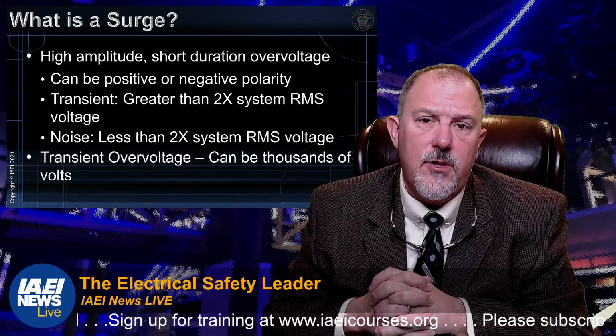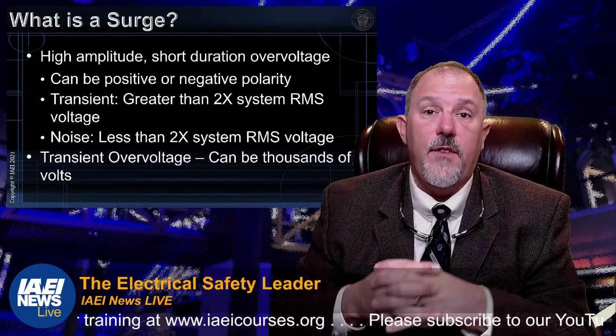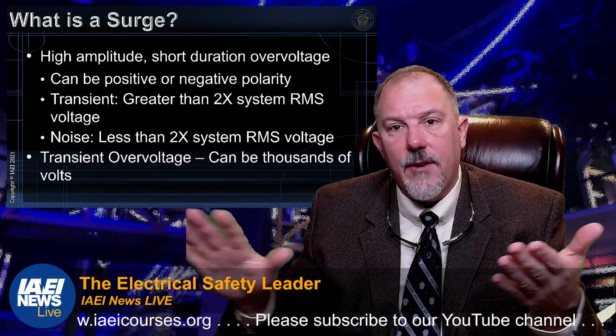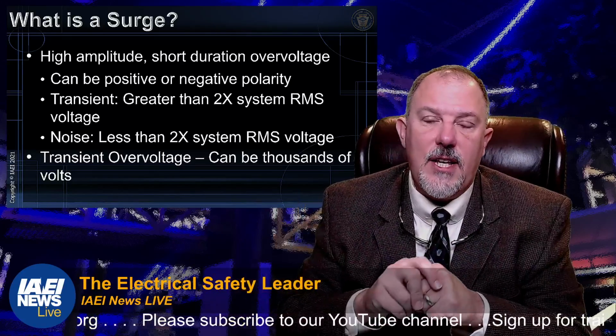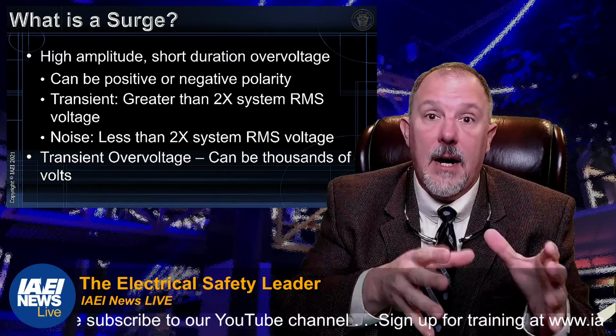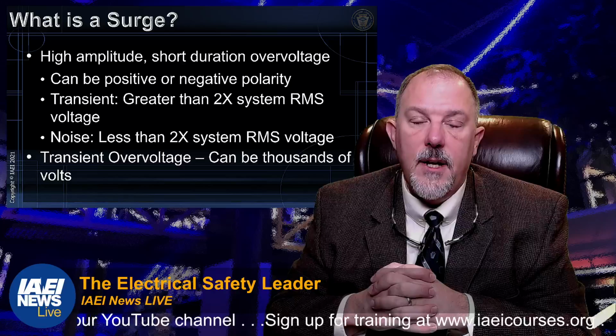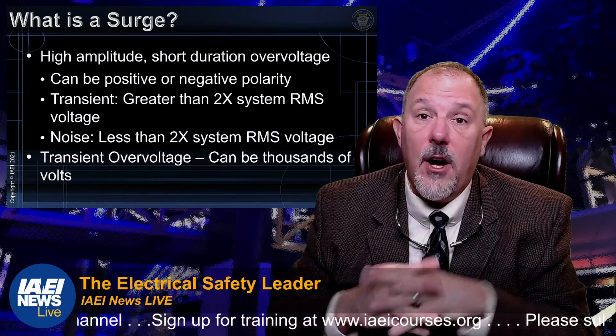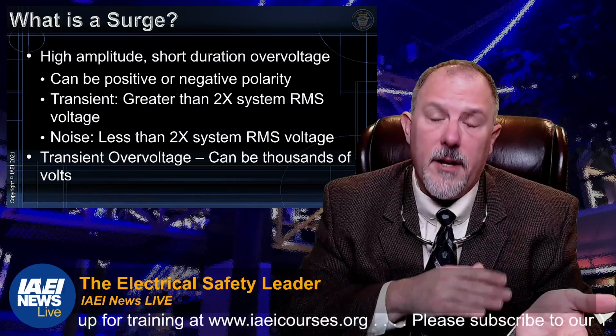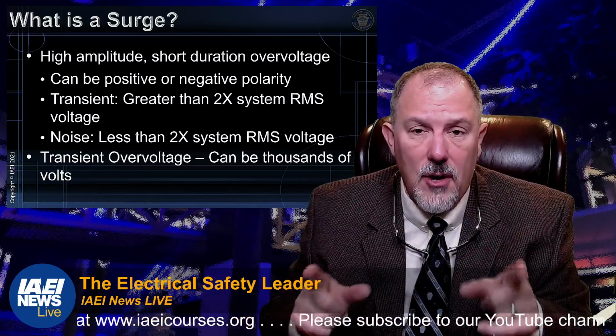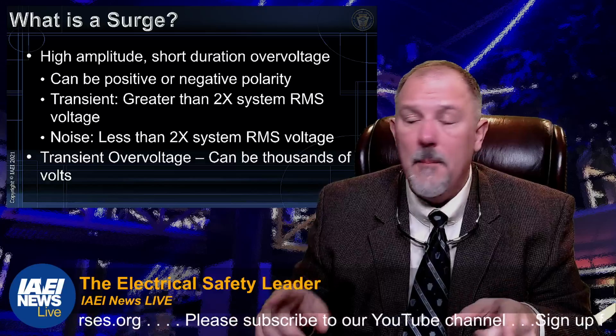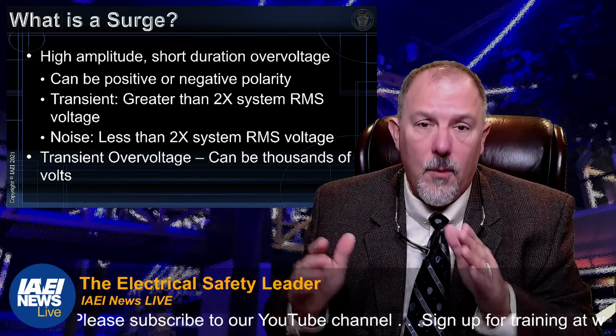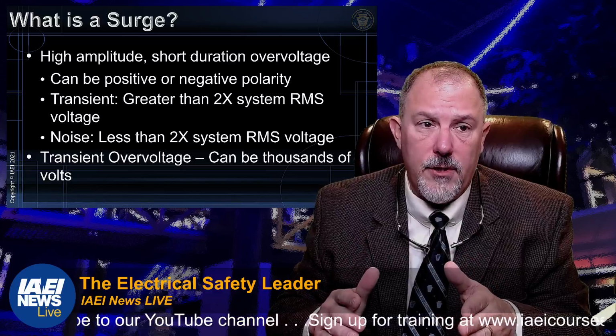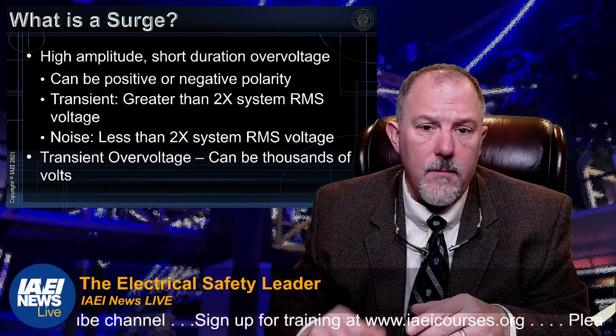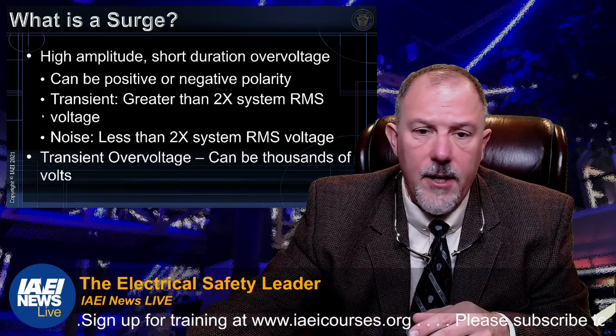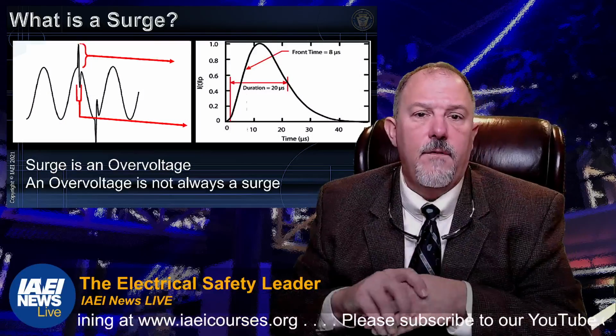That noise can be translated into various frequencies. If you broke that sine wave out into all of the different frequencies, you would see what is making up that voltage sine wave. Those higher frequencies have other effects that have harmonic concerns. And that too is a long-term issue in a power system, but a completely different discussion. What we're talking about are short duration overvoltages that occur. And again, a surge event can be thousands of volts.